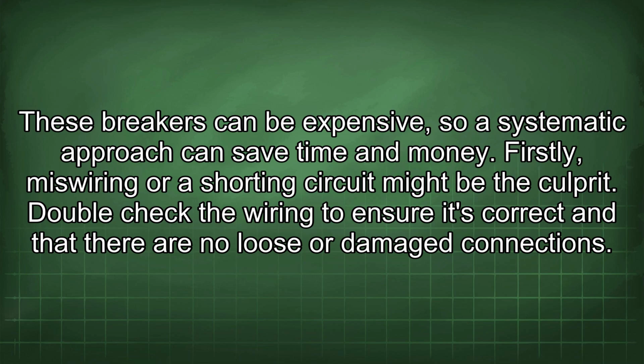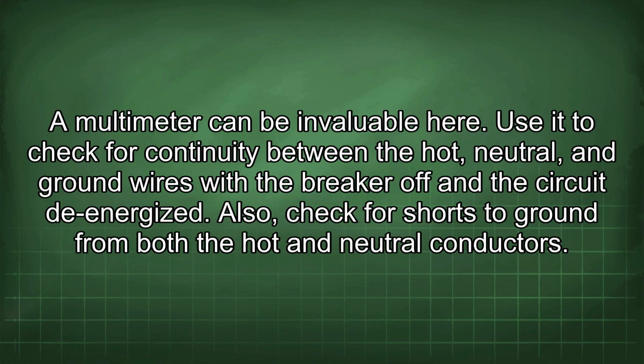Firstly, miswiring or a shorting circuit might be the culprit. Double check the wiring to ensure it's correct and that there are no loose or damaged connections. A multimeter can be invaluable here. Use it to check for continuity between the hot, neutral, and ground wires with the breaker off and the circuit de-energized. Also, check for shorts to ground from both the hot and neutral conductors.